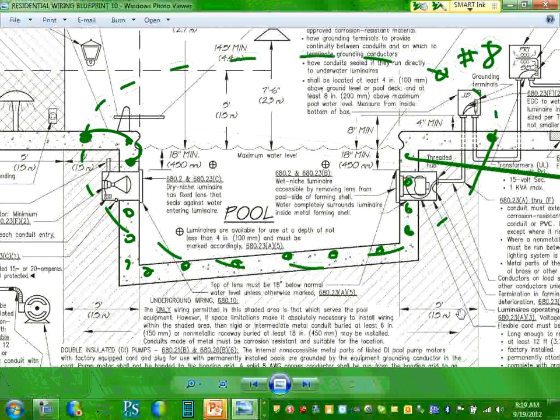And then anything mechanical: where's the diving board? Do I have the diving board here? It will be bonded to it. Do I see anything else in that one? The motor here will be bonded to it. The lighting fixture, guys, will be bonded through the grounding conductor, number 8, number 12. What else? Do I have a heating element? If I have a heater here, it is bonded to it with number 8. Any question, guys, about the swimming pool?